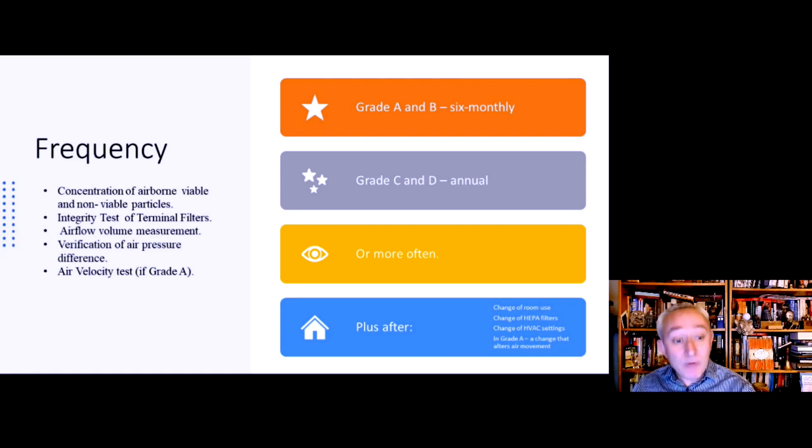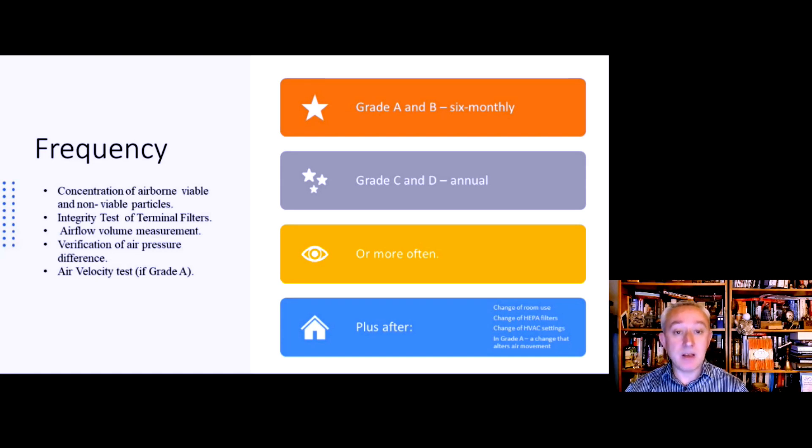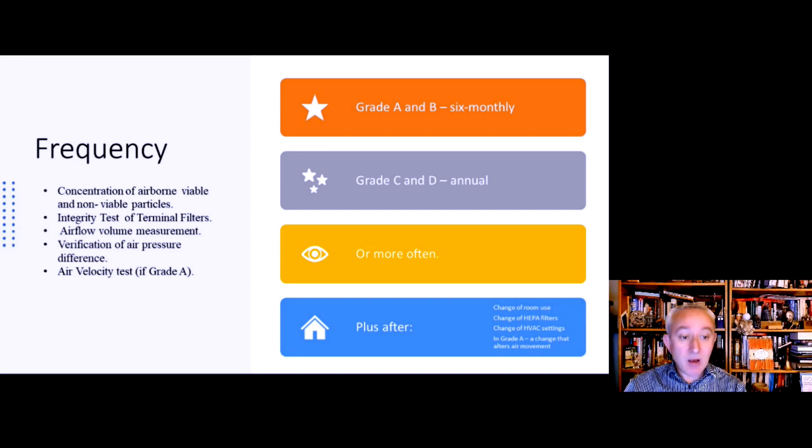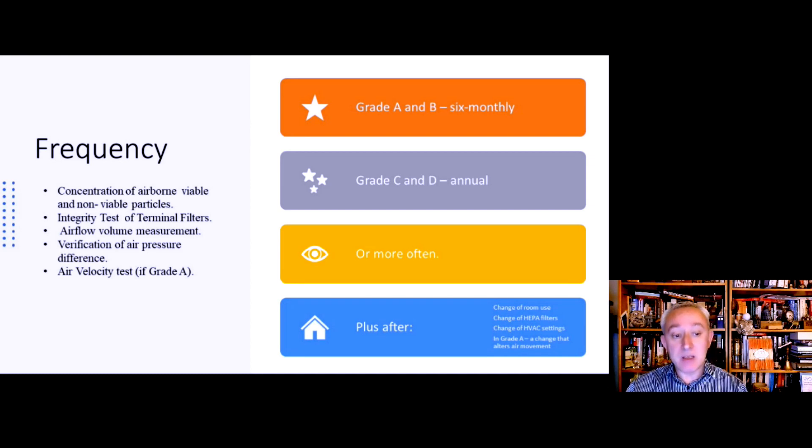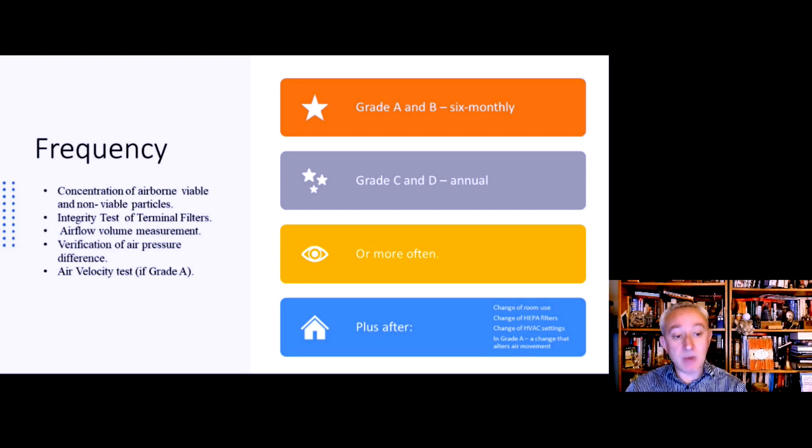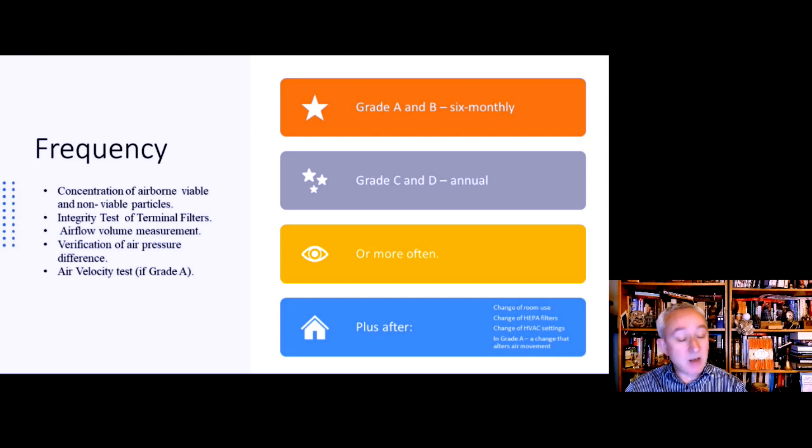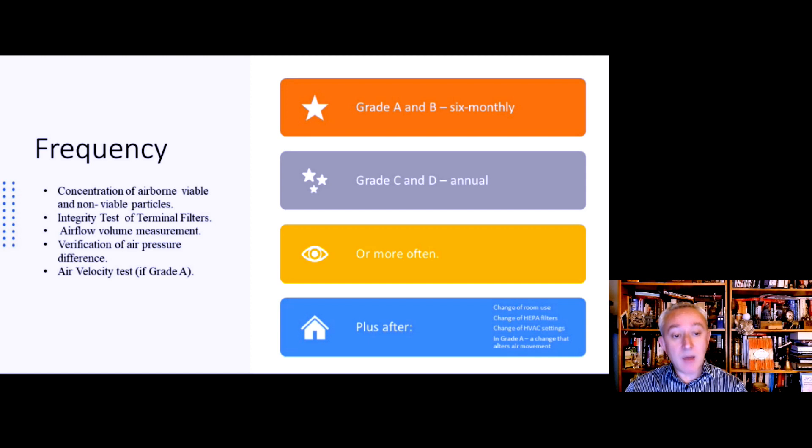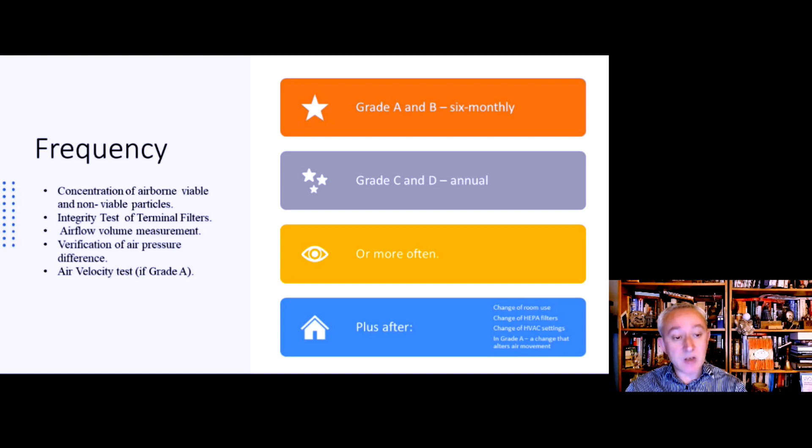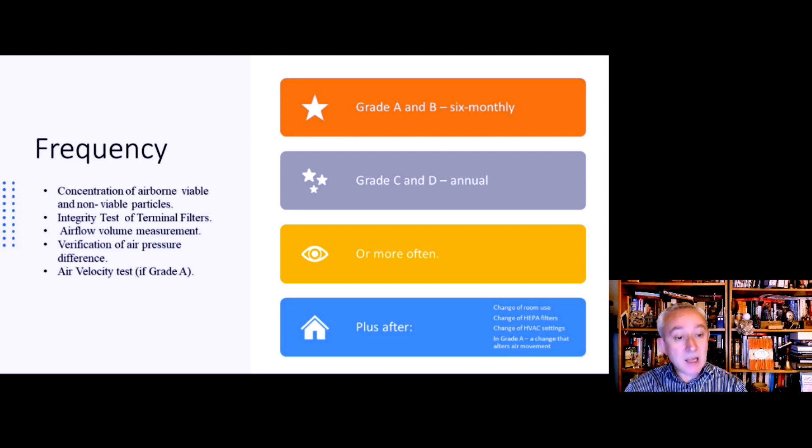In terms of how often all of this needs to be conducted: for grade A and B, the maximum time interval is every six months, and for grade C and D, the maximum time interval is every year. Of course, the Annex allows that to be done more often. It also describes situations when reclassification should be conducted, such as when we change the design space in the room and put it to a different use, or we change HEPA filters, or we make some other change to the heating, ventilation, and air conditioning (HVAC) settings. In grade A, if there's anything done that changes the air movement or if we were to make an adjustment to the airflow velocity.